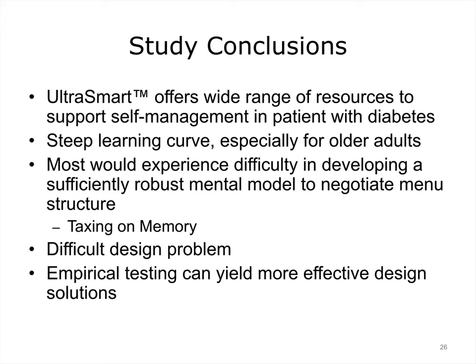In conclusion, the glucose meter offers a wide range of resources to support self-management in patients with diabetes. However, mastery is associated with a steep learning curve, especially for older adults, as most users would experience difficulty developing a sufficiently robust mental model to negotiate the complex menu structure. This is a difficult design problem given the size of the screen and limited interaction possibilities — for example, there is no keyboard or mouse. Usability testing can be used to glean more effective design solutions and weed out suboptimal design dimensions.